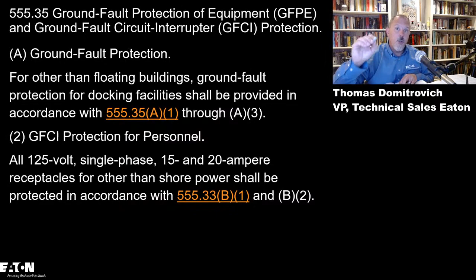So now, A talks about ground fault protection. For other than floating buildings, ground fault protection for docking facilities shall be provided in accordance with A1 through A3. We already said that. So now we're on 3. So we did 1, we did 2. Remember, 1 was actually the shore power, right? That was the 30 milliamps. A1 was 30 milliamps. That was your shore power. A2 was your receptacles, 15 and 20 amp receptacles, and anything in accordance with 210.8. And then 3 talks about your feeders.